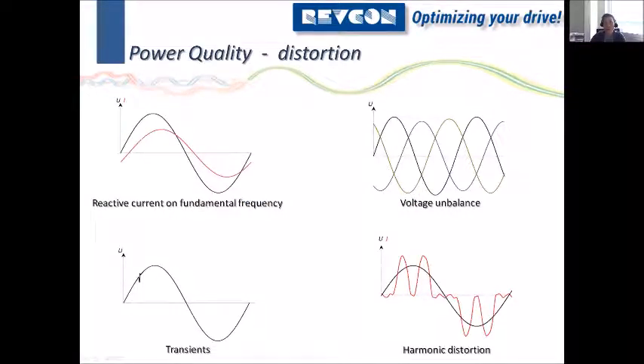First of all, I want to show you a quick overview of the typical power quality issues we face worldwide. We have the reactive current, which is what you would typically see when you connect a motor direct online. As this takes a reactive current, you would always see some kind of displacement between current and voltage. We have voltage imbalance if you have an unsymmetrical loaded system. We have transients, which is typically a single or a periodical event on the main supply, so when you turn on something very strong, or maybe for some other reasons, you may have transients. And we have the harmonic distortion, which is the topic of today.